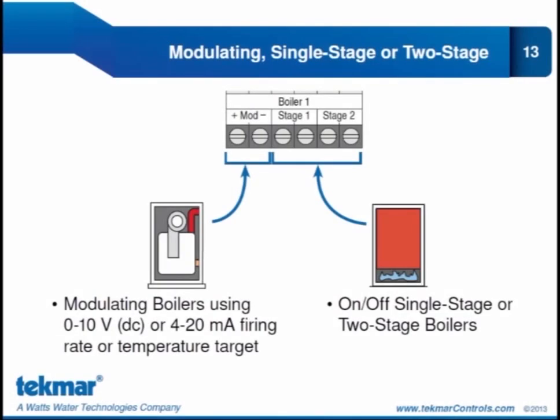Up to 4 boilers are independently configured on the 284. It's difficult to find proper control for different types of boilers, but the 284 is flexible enough to operate boilers that are either modulating, single stage, or two-stage. This truly is a control that can be customized for your particular boiler plant design.